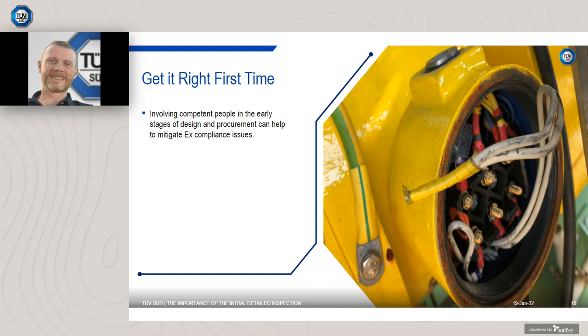The manufacturer of the Ex d unit in the photo has taken steps to design and have certified a product. The installer has not shown an understanding of either the standards or project specifications. Note the spare cores taped and coiled within the unit. Nor has he ensured that the equipment was preserved, taken care of, while in his facility. Note the rust on the flame path.